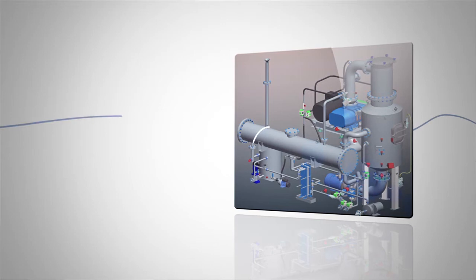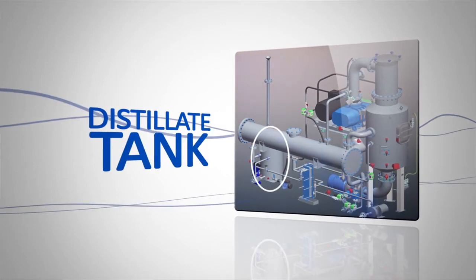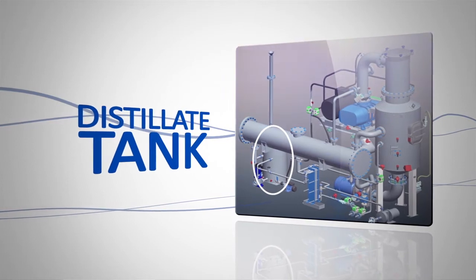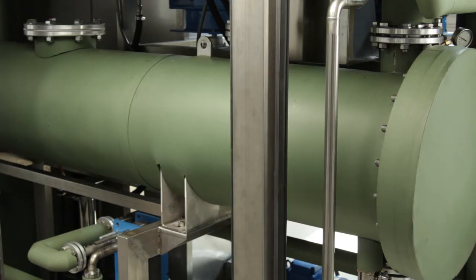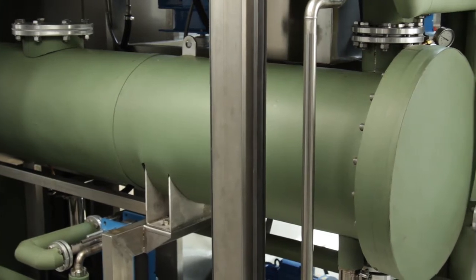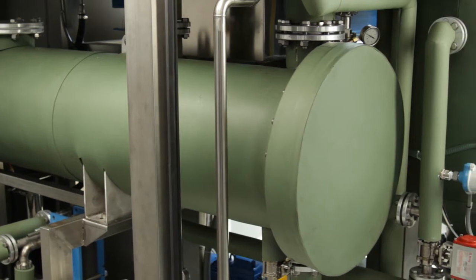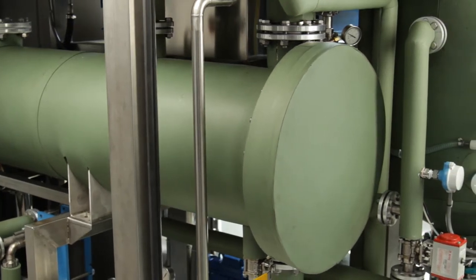The distillate tank merits a look as well. You can see it is separate from the condenser. The separation of the two components allows the choice of a floating head condenser instead of a stationary one. Thanks to the floating head condenser, the shell and tubes can be completely extracted and this feature allows the treatment of even fouling wastewater types.